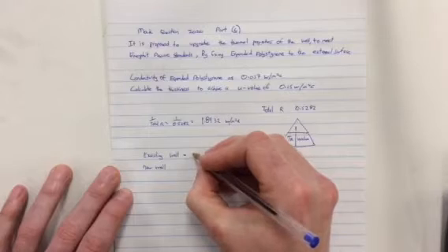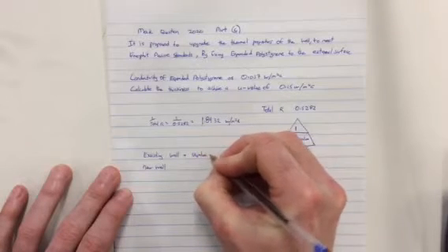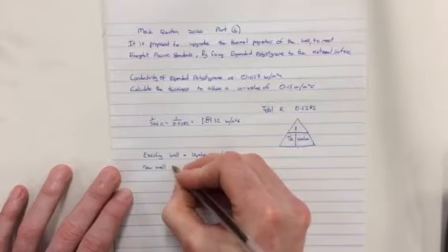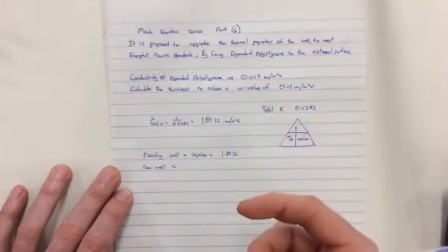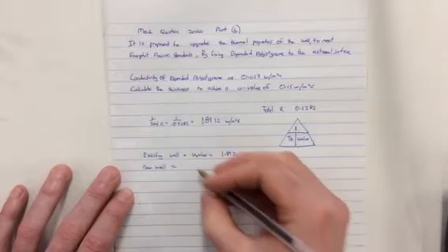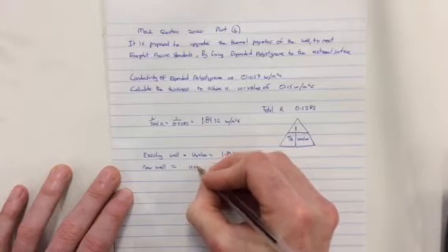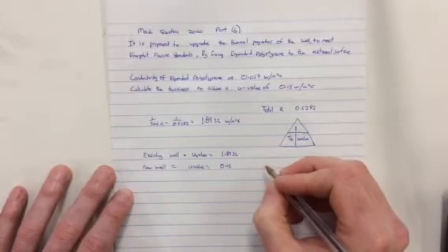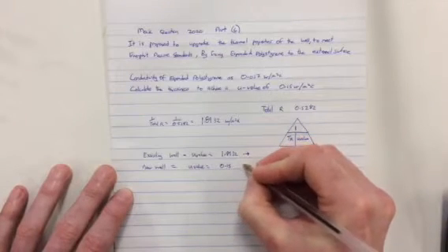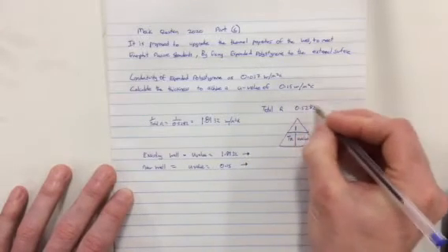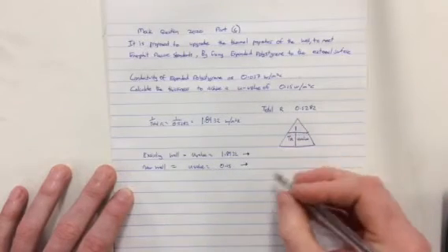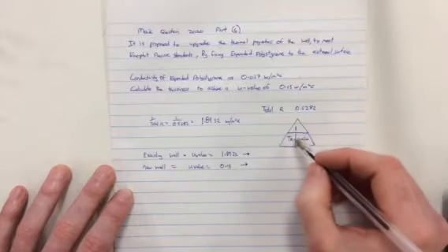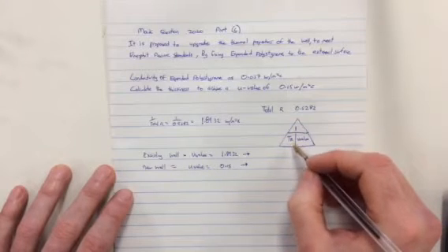So the existing wall U value is 1.8932. For the new wall, the U value we're looking to get is 0.15, a big difference. Then we're trying to find the resistance of both. So we're trying to get back up into this column that would be on your table above that.